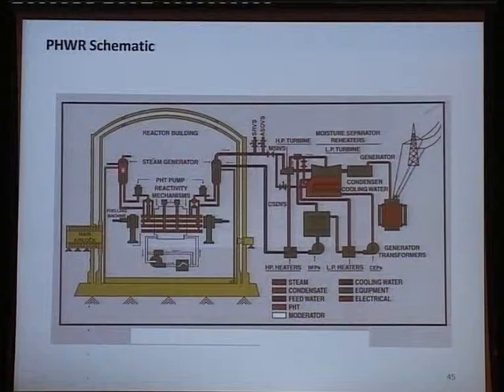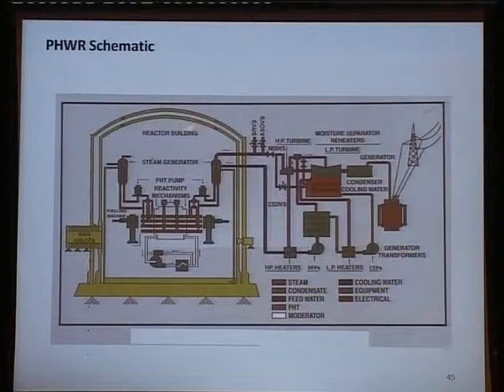Here also the configuration allows us to maintain a certain degree of thermosiphoning, that is natural convection cooling. In all our cases we provide what we call double containment. The inner reactor building is made of pre-stressed concrete to withstand high pressure. There is a second building that can actually withstand an aircraft impact. The space in between is kept at negative pressure so that any leakage goes into that space, and the air is put through filters to remove radioactive substances before being let out.